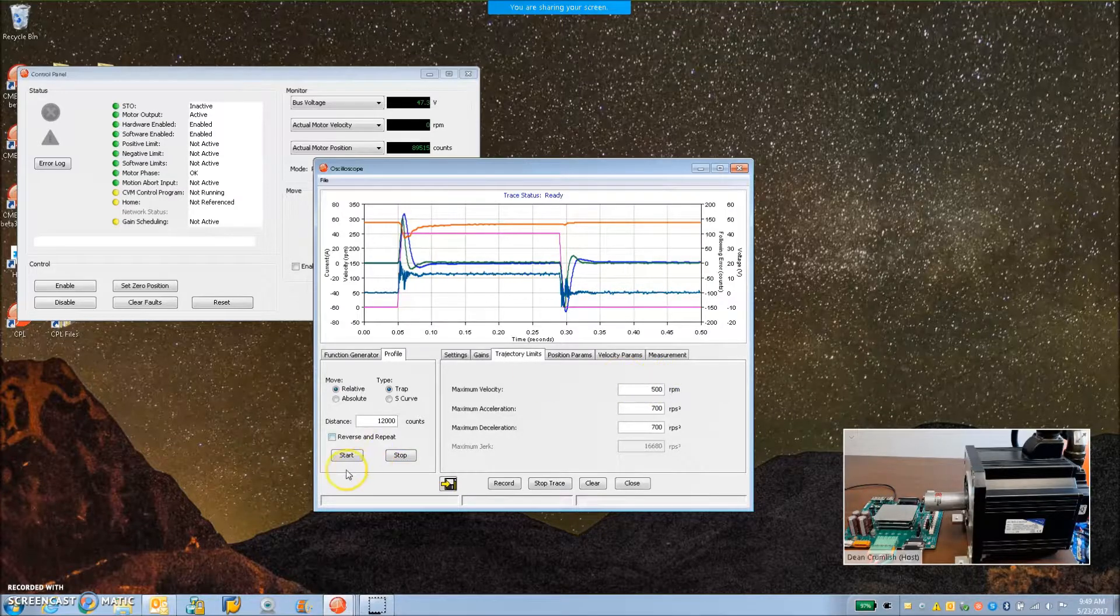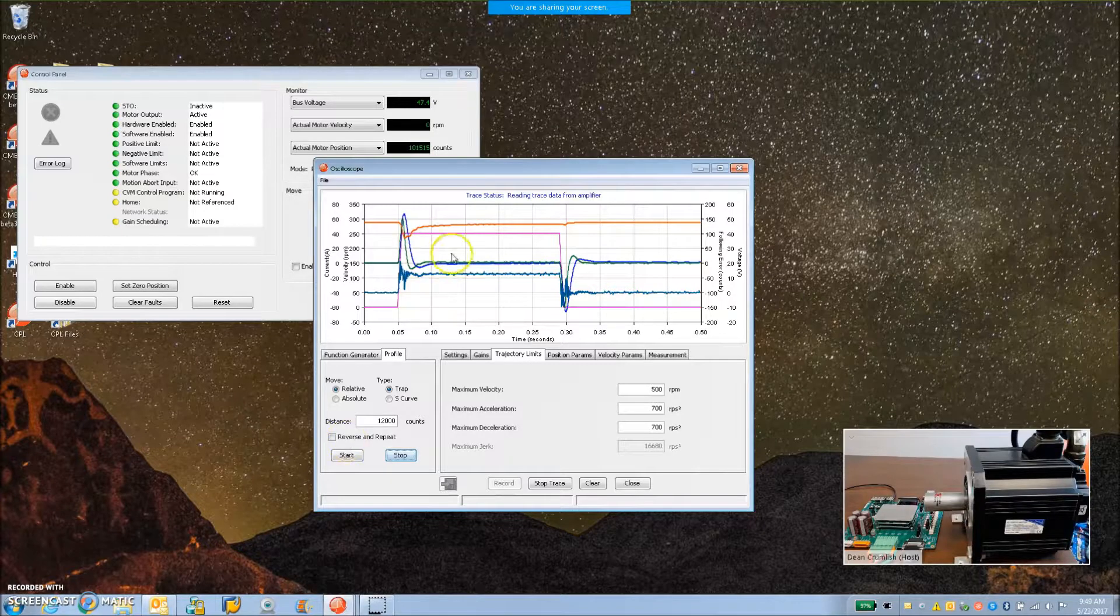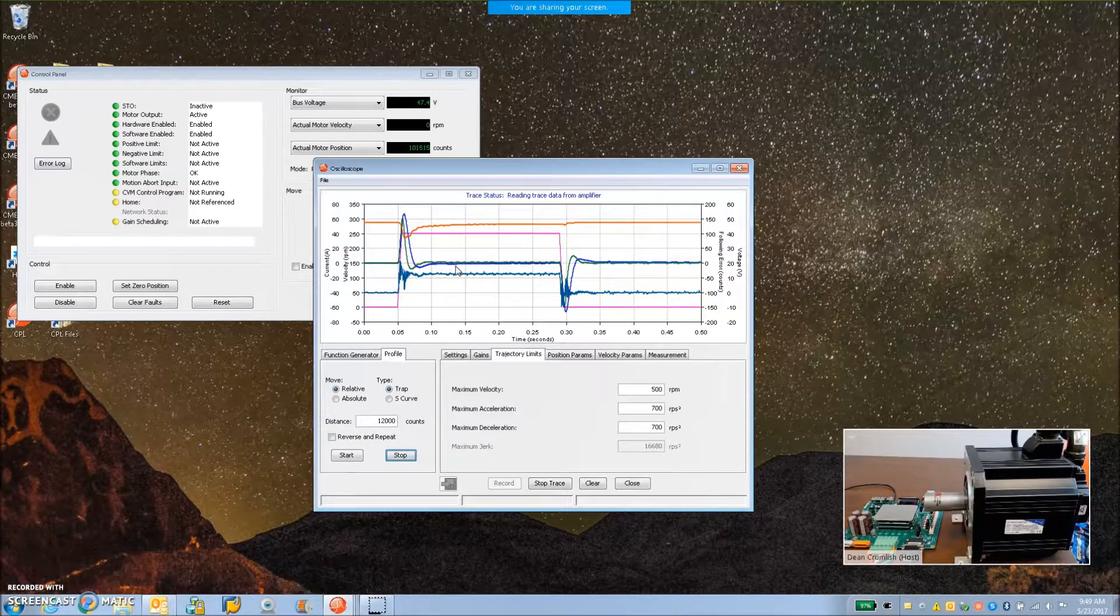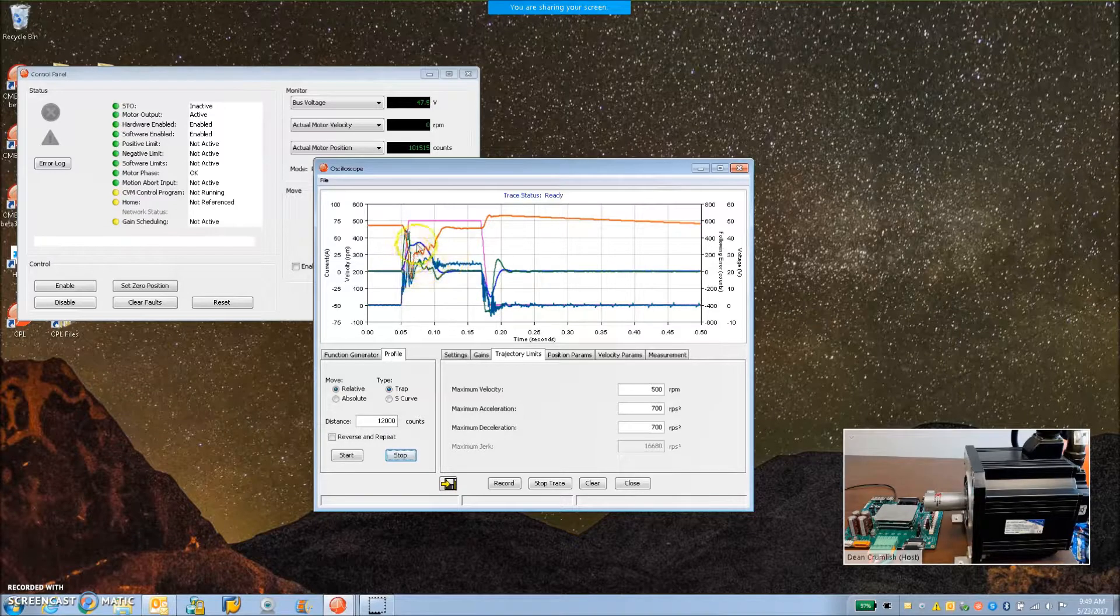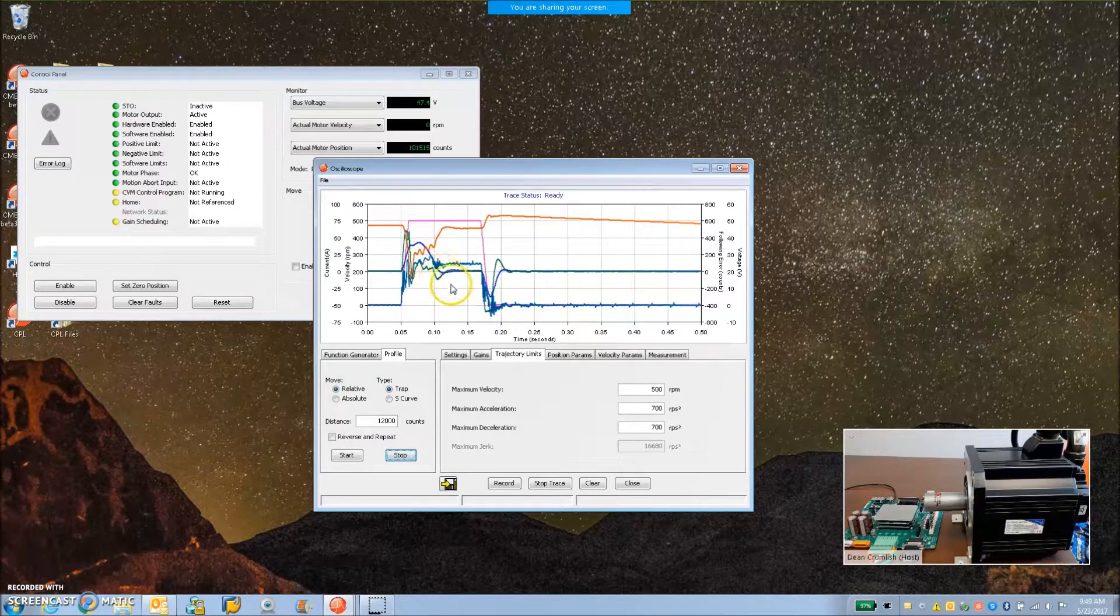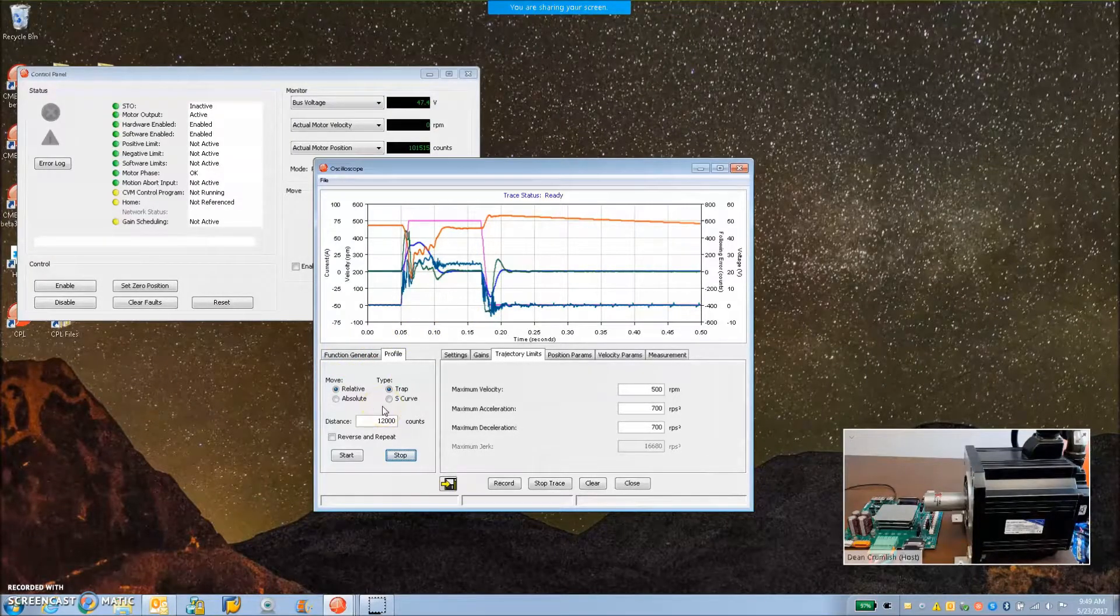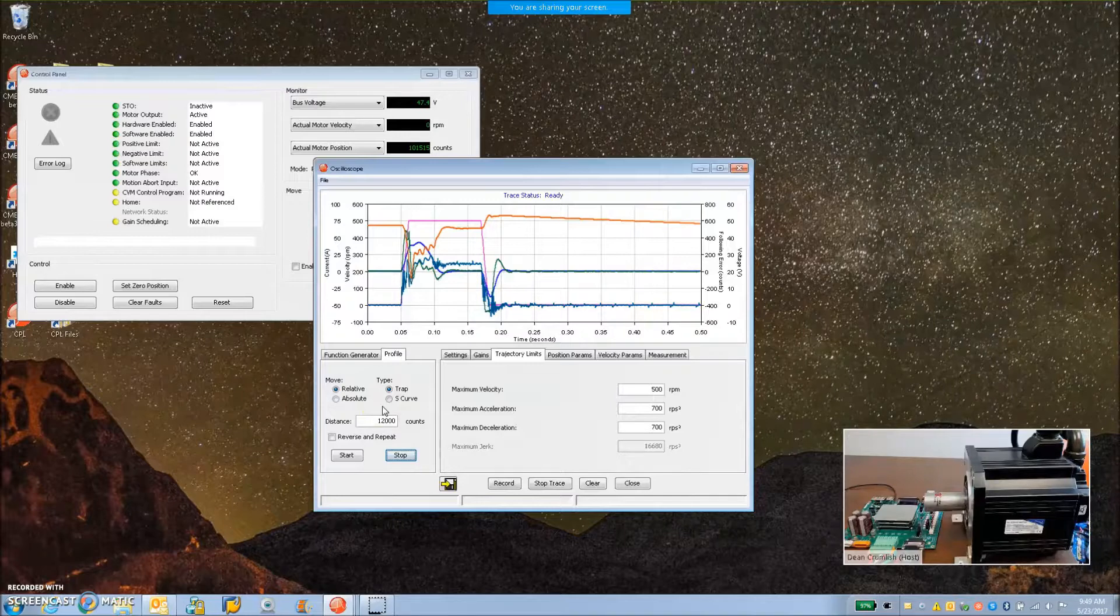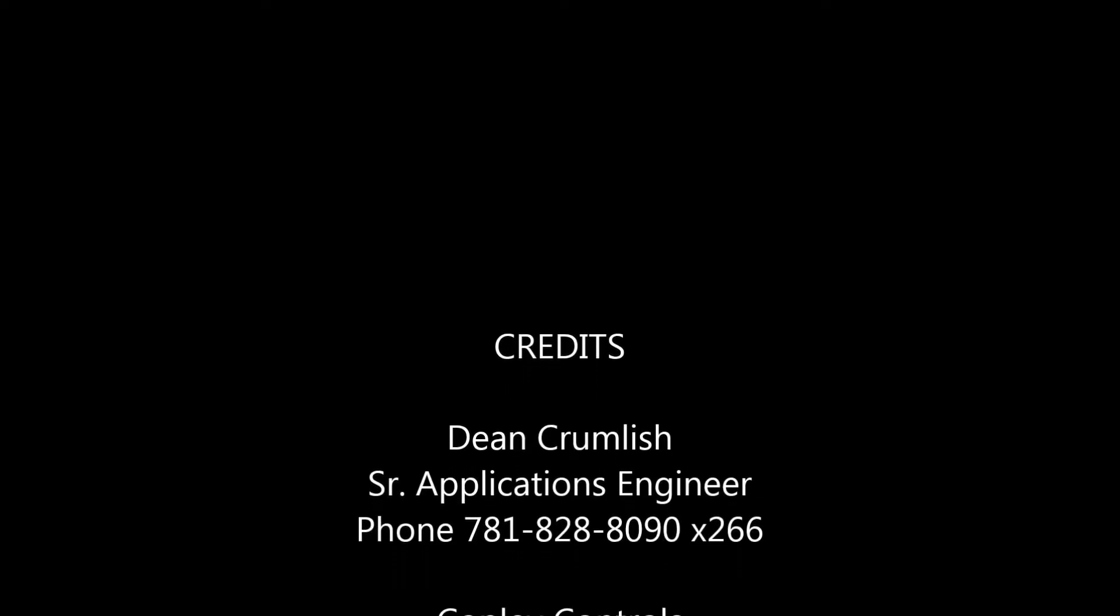But you can trace the terminal voltage, see how bad your back EMF limit is, and I'm going to show it going too fast here. So we have to watch out for a voltage limit. So yeah, we're starting to get voltage limited here and the following error builds up. So this motor requires a higher voltage. I think it's a 200 volt motor. You can get different windings or you can get a... Thanks for watching.